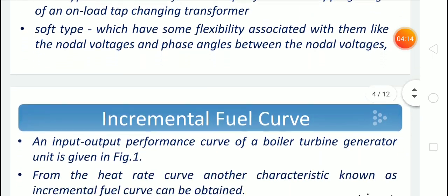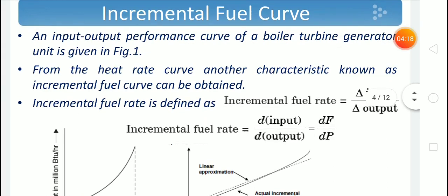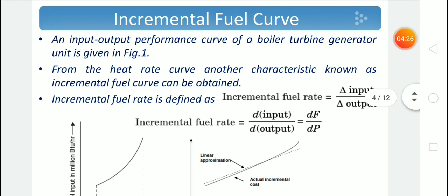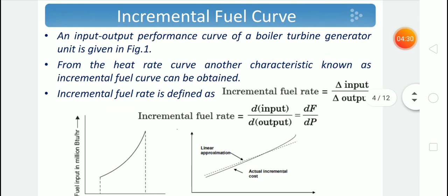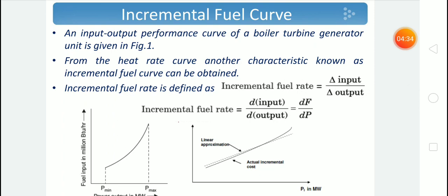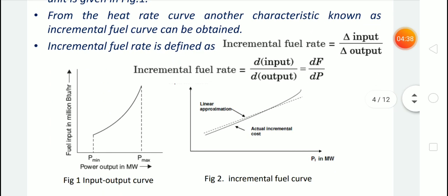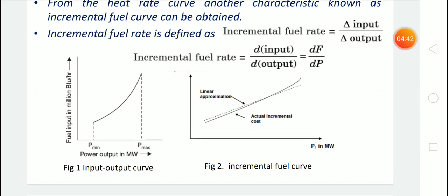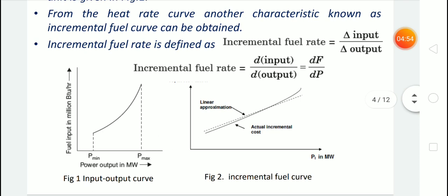Now we can move on to the economic load dispatch problem. One of the important parameters is incremental fuel cost. For finding the incremental fuel cost, we draw the incremental fuel cost curve. Figure 1 shows a fuel input versus power output curve — an input-output curve, which is a parabolic curve. If we differentiate this, we get the incremental fuel curve. The incremental fuel rate is the change in input divided by the change in output. When we differentiate the fuel input-output curve, we get the incremental fuel curve, which is almost linear.